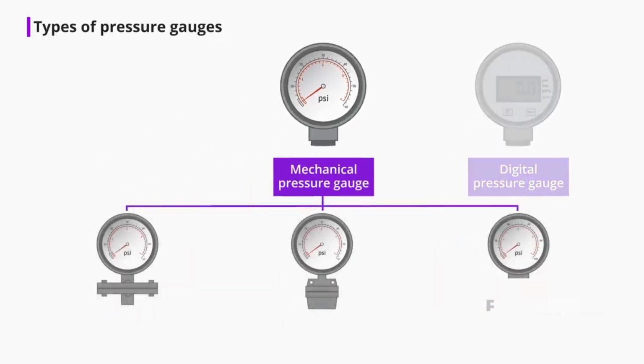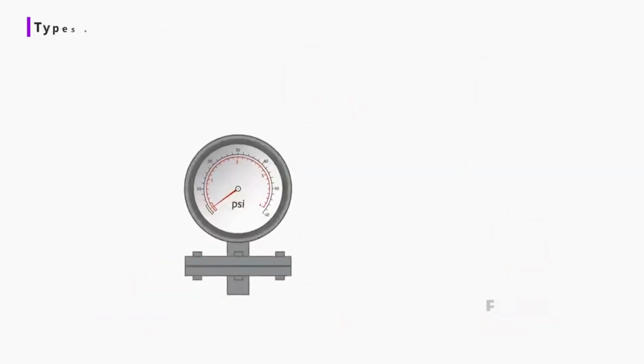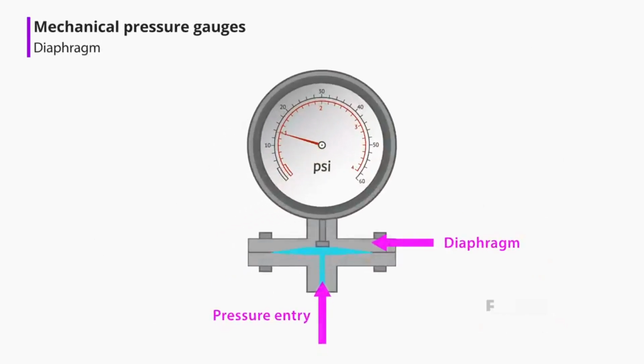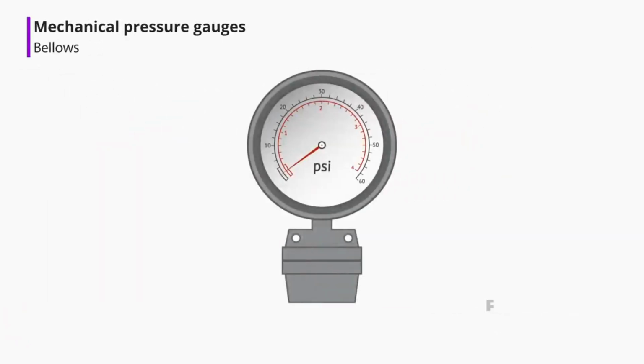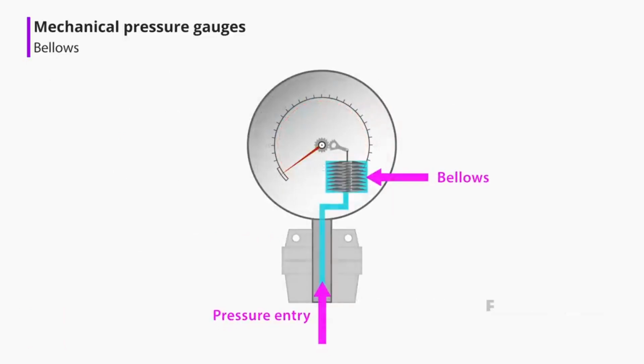There are many types of mechanical pressure gauges. Three of the most common types are the diaphragm, bellows, and Bourdon tube. A diaphragm pressure gauge uses the deflection of a flexible thin membrane called the diaphragm to measure the pressure of the fluid in a system. A bellows is a corrugated expandable device made up of corrugations or ribs called convolutions. The bellows are usually brass or stainless steel and very sensitive. Pressure is applied to the bellows, causing it to expand, which in turn moves a pointer.